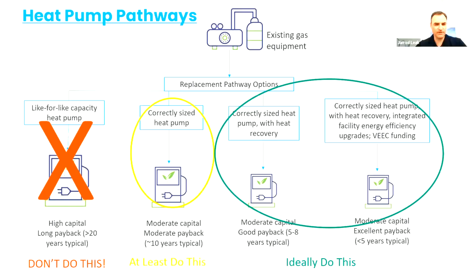Chris, we're really looking at a dramatic difference there. You're saying greater than 20 years if I've just got that 1 megawatt steam boiler and I go to replace it with a 1 megawatt capacity heat pump, that's going to be around 20 years. But if I take these steps, I'm getting down below 5 years. Totally possible, and certainly with increasing gas prices as well, those paybacks come down even further.